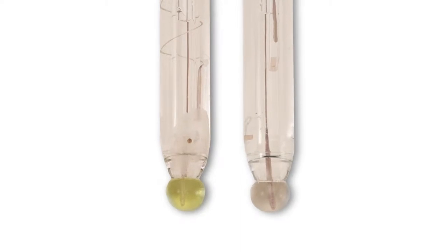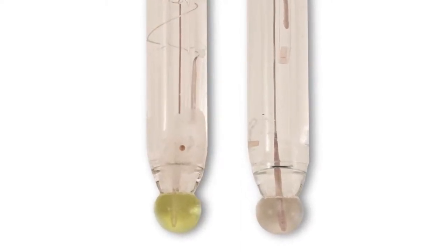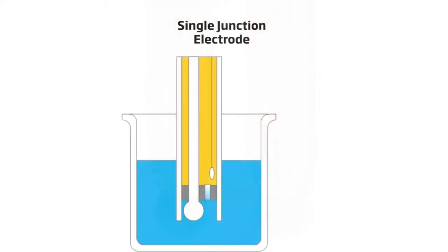Hanna Instruments manufactures single and double junction pH electrodes. In single junction electrodes, the silver-silver chloride reference wire is surrounded by a 3.5 molar KCl solution with silver chloride.